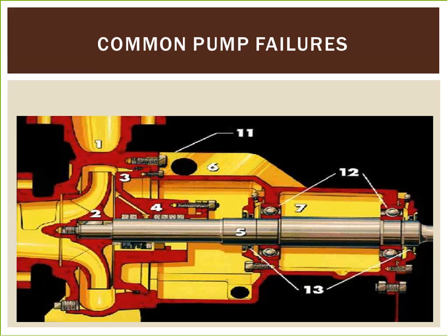Common pump failures relate to leaks. The pump could leak externally from a seal or gasket at the supply and return hookups. It could leak internally at the shaft seal, as shown with the number 2. The shaft is where the drive portion connects to the pump section. If the shaft seal leaks, fluids can get into the drive section.